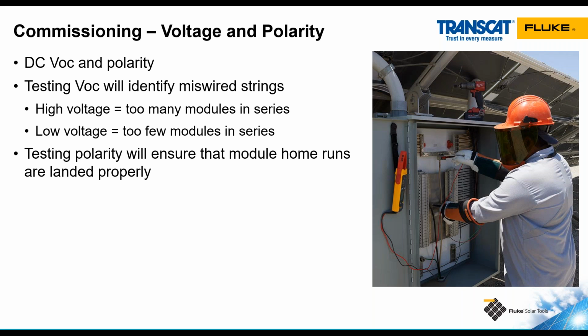If we do polarity testing at commissioning before we have closed the fuse holders, we can identify polarity issues before they become a problem. So if someone connected a positive and negative conductor to the positive bus bar, with the fuses open, that's an open circuit.